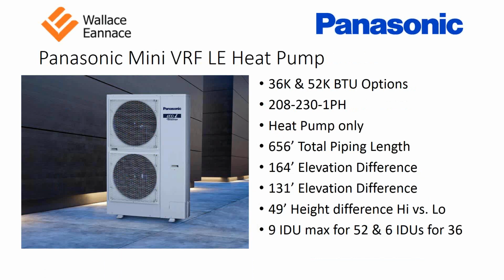Our elevation difference for our refrigerant piping is 164 feet when the condenser is on the roof, and when the condenser is on the ground outside, it's 131 feet that you can pipe up a building inside. The height difference, high versus low, on the indoor units: our highest indoor unit can only be 49 feet above our lowest indoor unit on one condenser, piped back to one condenser. We can connect 9 indoor units max to the 52,000 BTU unit, and we can connect 6 indoor units max on the 36,000 BTU unit.